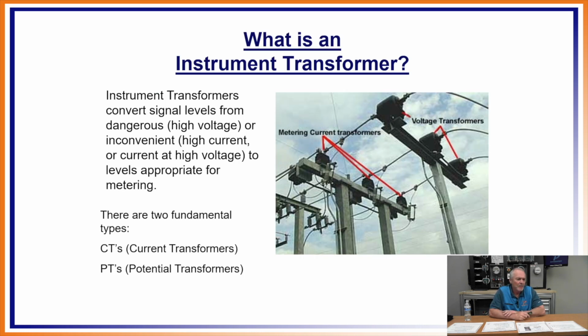So what is an instrument transformer? Well, you can see up here in the example, where the red arrows are, we've talked about this a lot, and it's very important to you and me from a safety standpoint, and for the size of the equipment we have to deal with at the bottom of the pole. They take high levels to lower levels, so we always deal with step-down transformers, typically. In this case, as Steve has put here, instrument transformers convert signal levels from dangerous or high voltage, or inconvenient high current or current at a high voltage, to levels appropriate for metering. So the two step-down transformers that we typically use are CTs and PTs.